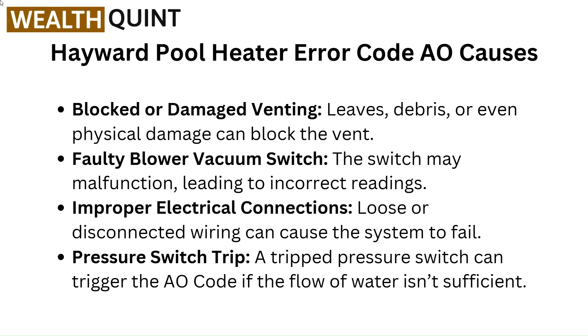Faulty blower vacuum switch — the switch may malfunction, leading to incorrect readings. Improper electrical connections — loose or disconnected wiring can cause the system to fail. Pressure switch trip — a tripped pressure switch can trigger the AO code if the flow of water is not sufficient.